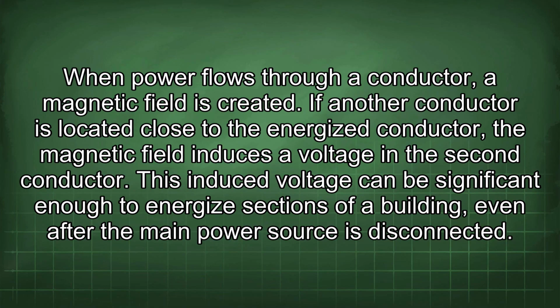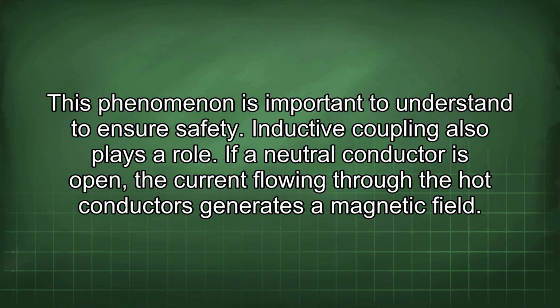When power flows through a conductor, a magnetic field is created. If another conductor is located close to the energized conductor, the magnetic field induces a voltage in the second conductor. This induced voltage can be significant enough to energize sections of a building, even after the main power source is disconnected. This phenomenon is important to understand to ensure safety.